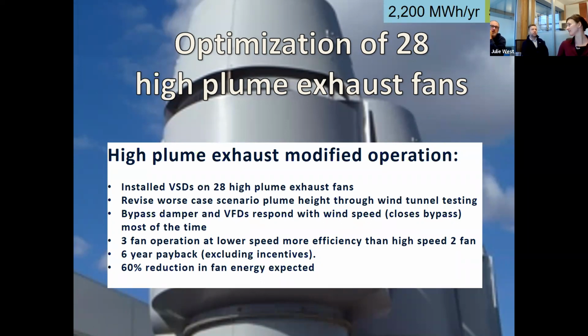Do you have anything else? Well, it's way more complex. I mean, it's hard to fit it into a slide, but with the wind modeling, we had to add an anemometer to the roof of the building, which takes wind speed and direction. That is mapped and put into our BMS system. So we're constantly measuring the direction and the speed of the wind, and we're modulating the strobic systems to ensure that we have good dispersion and still maintaining duct static for the building.